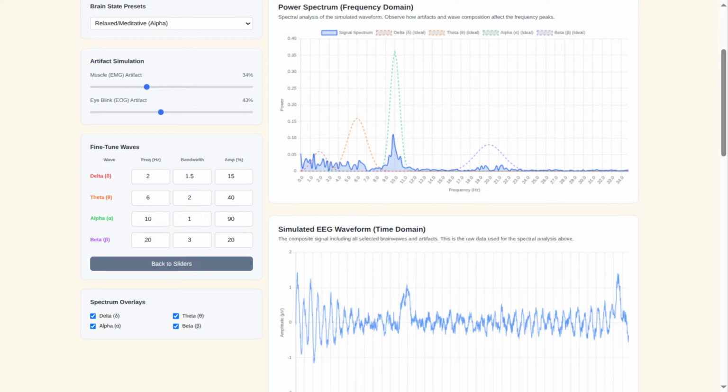So take a pattern clinicians look for called burst suppression. This is a really serious sign, often meaning severe brain injury, deep coma. It's a critical finding. It leads to huge decisions, withdrawal of care, even brain death declarations sometimes. So the stakes couldn't be higher. What happens with this LFF filter then? Well, this is where it gets kind of shocking. The research clearly shows that by simply adjusting that low-frequency filter setting, maybe turning a virtual dial, that exact same piece of raw EEG data can be made to look like continuous slow-wave activity.